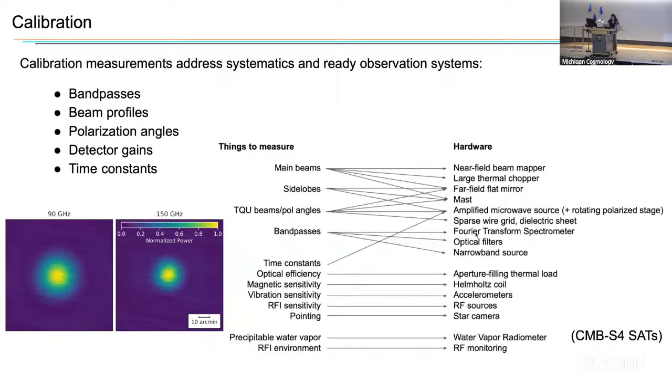And I'm not going to read all of these words. You can go back and read all these words. One thing I'll just point out is that this is a planet scan. We do these to check our system both in commissioning when we're first setting up a new instrument and also later to make sure we're staying calibrated over time.